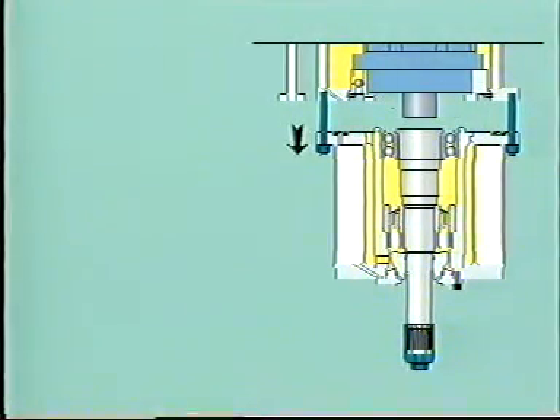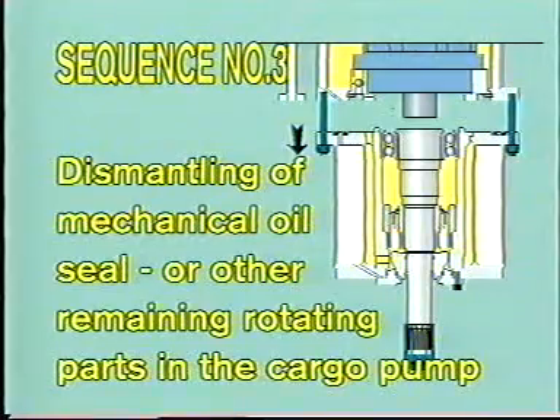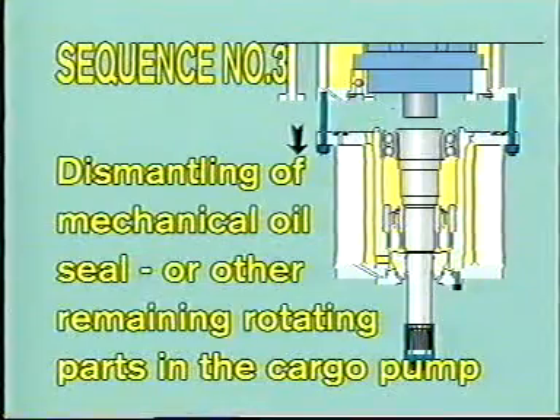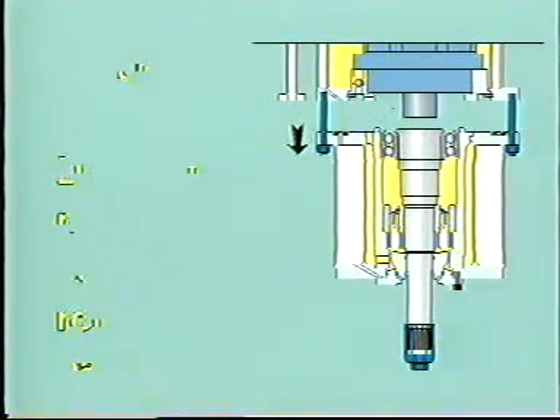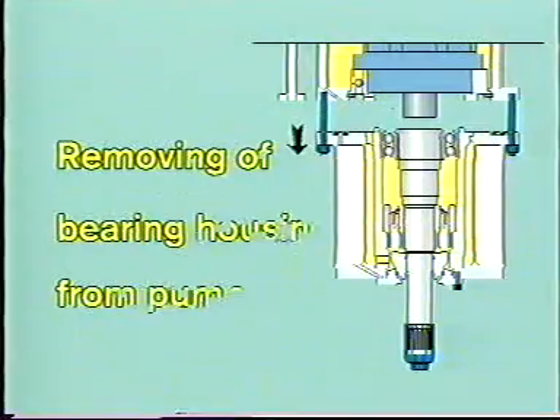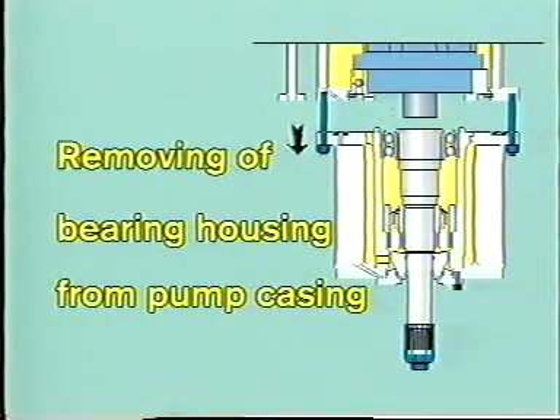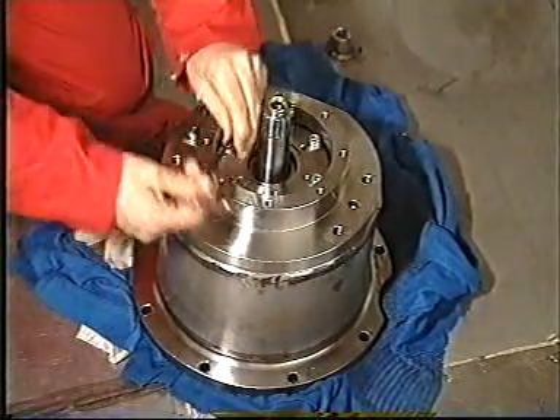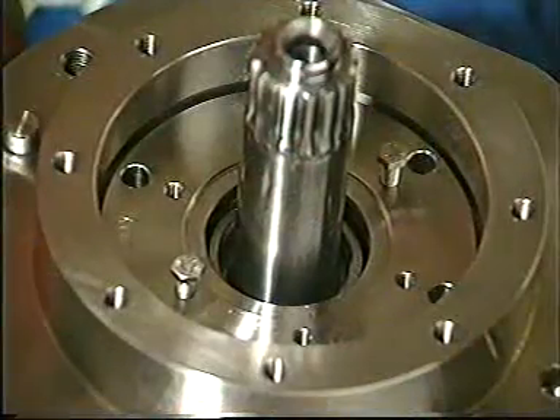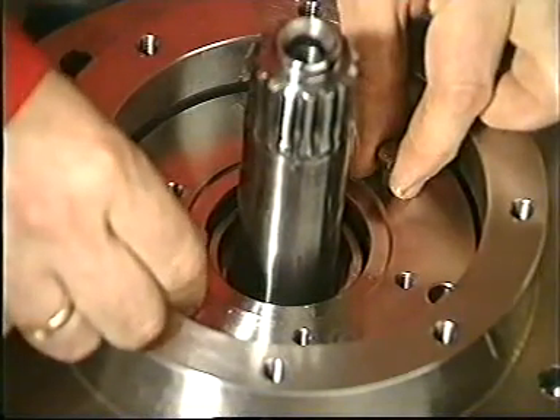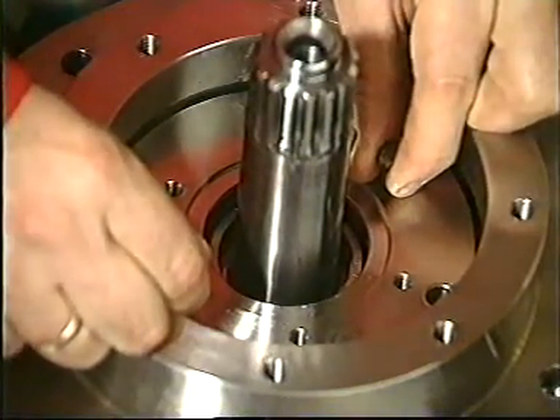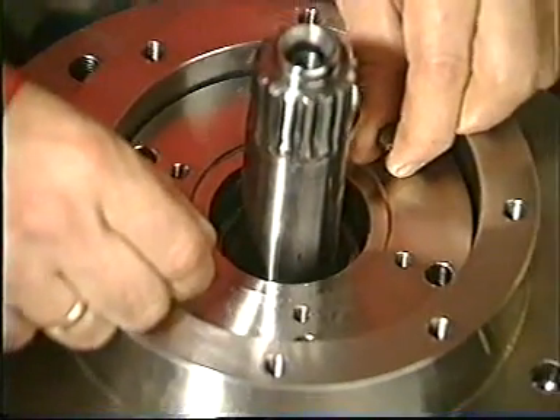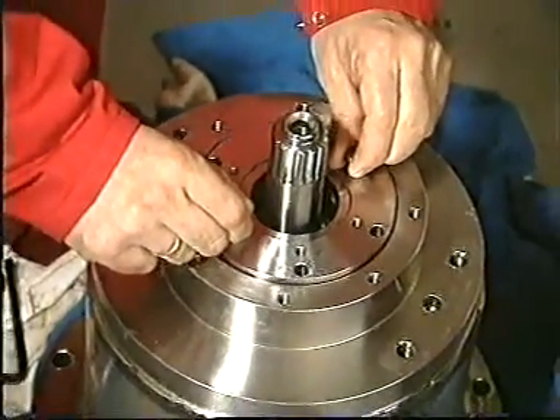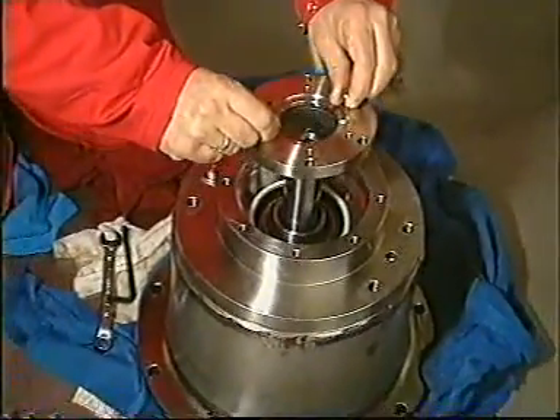Sequence number 3. Dismantling of mechanical oil seal or other remaining rotating parts in the cargo pump. The mechanical seal can be dismantled without draining the hydraulic oil from the pump stack. The easiest way to dismantle the mechanical seal is first to remove the bearing housing from the pump casing. When the unit is dismantled, turn it upside down and remove the upper seal ring housing and then the stationary parts of the mechanical seal. Use 2 lifting bolts to take out the mechanical seal.